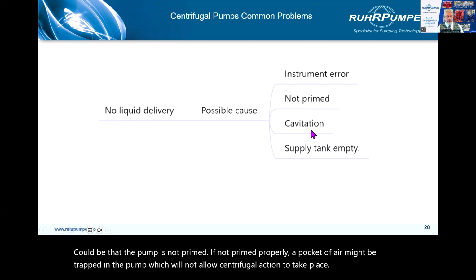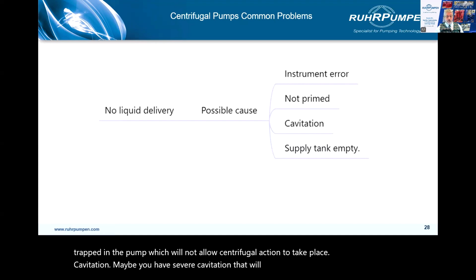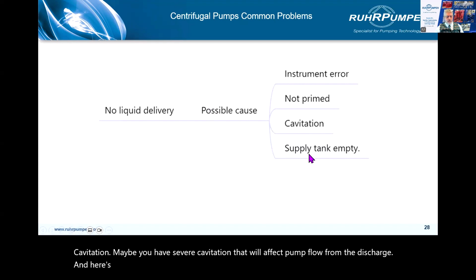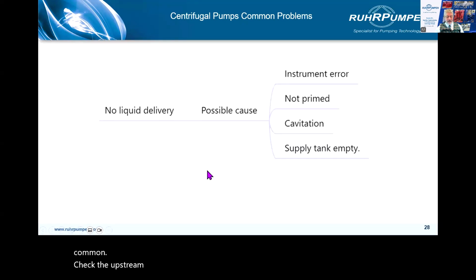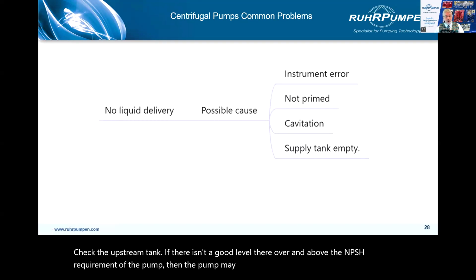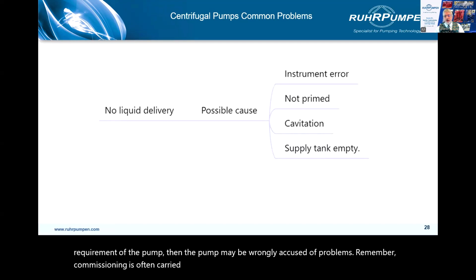Cavitation. Maybe you have severe cavitation. That will affect pump flow from the discharge. And here's an important one. Supply tank empty. Again, sounds obvious, remarkably common. Check the upstream tank. If there isn't a good level there over and above the NPSH requirement of the pump, then the pump may be wrongly accused of problems. Remember, commissioning is often carried out with a partially filled system, so it might well be that the supply tank is not full.